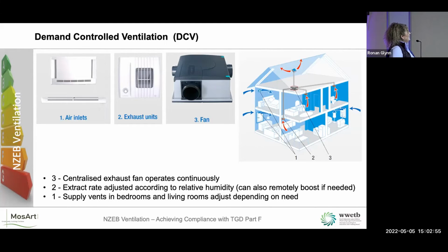The thing about this is you have to be careful that your house stays in balance all the time. You've technically gone below the general ventilation rate, which is why they've produced their Agrément cert. You still have to be very careful that you're not in a negative pressure. Again, there's no heat recovery.